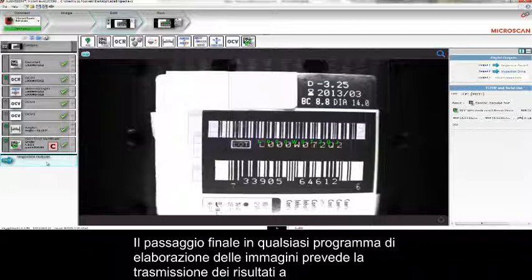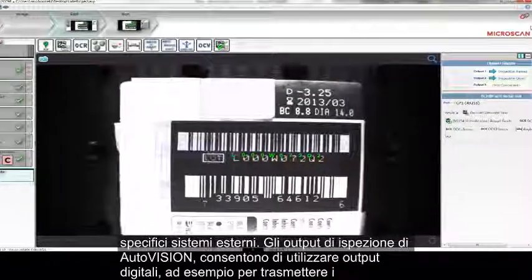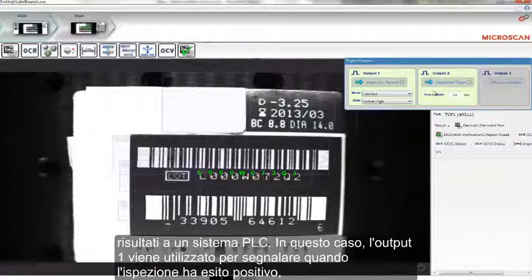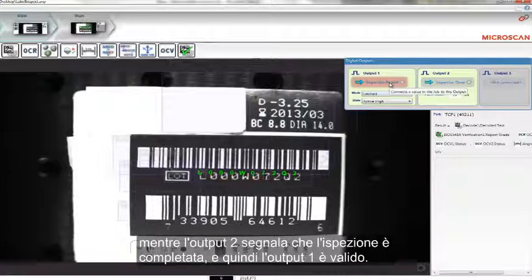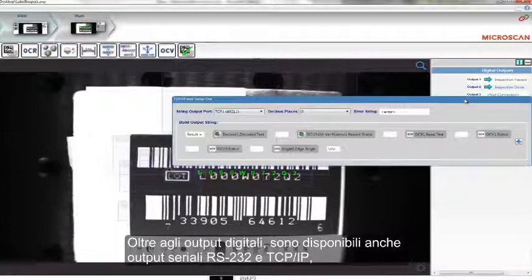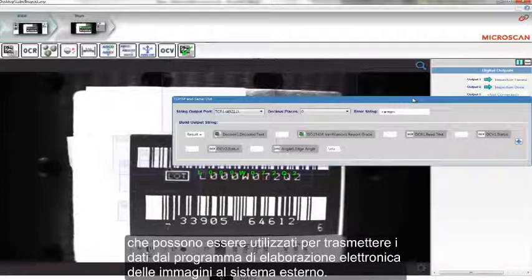The final step in any program is to report the results to the outside world. In AutoVision, the inspection outputs allow you to use digital outputs — for example, to send the results to a PLC system. Output 1 is used to signal when the inspection passes, and Output 2 signals that the inspection is completed, so Output 1 is valid. In addition to digital outputs, there are also RS-232 and TCP-IP serial outputs that can be used to report information from the Machine Vision program to an outside system.